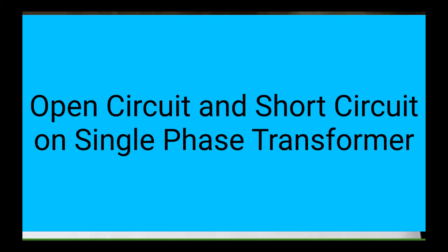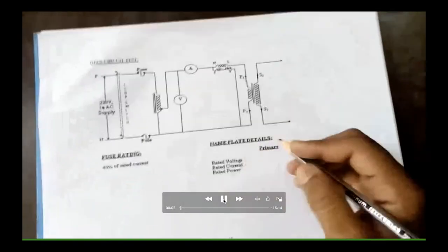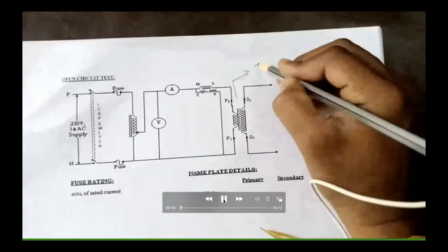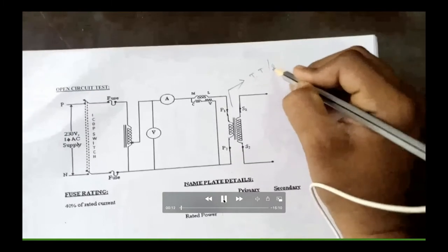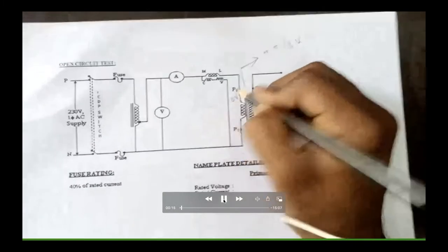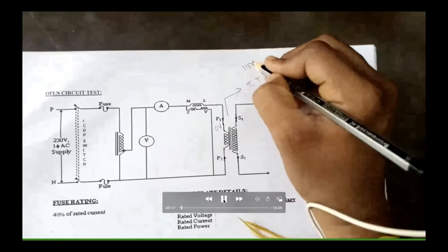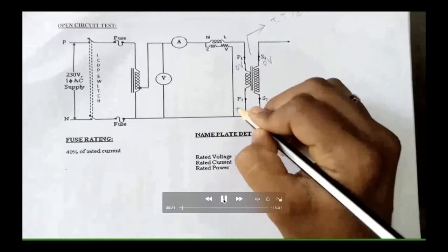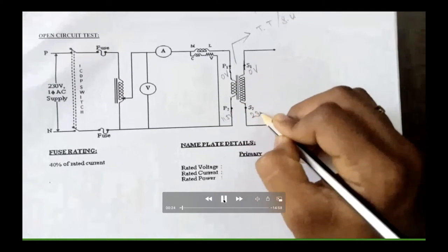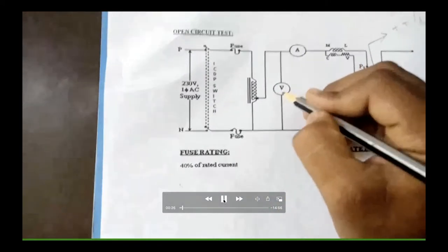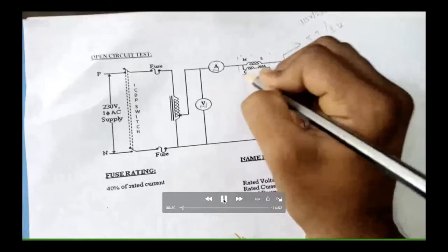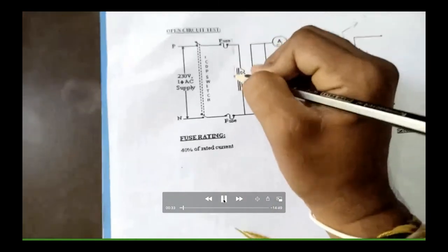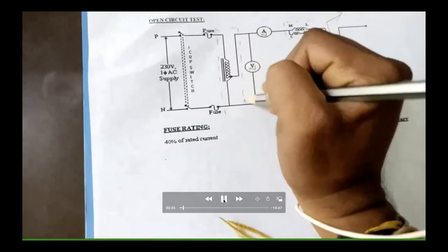Next, we discuss the open circuit and short circuit test on a transformer for the students. So this is the open circuit diagram. We have the primary winding and secondary winding. The primary voltage is 0 volt, 115 volt, or 230 volt. On this side it is 0 volt, 115 volt, and the secondary side is open, 0 volt and 230 volt. So we have the primary voltmeter, ammeter, a wattmeter, and an auto transformer, or we call it the variac.